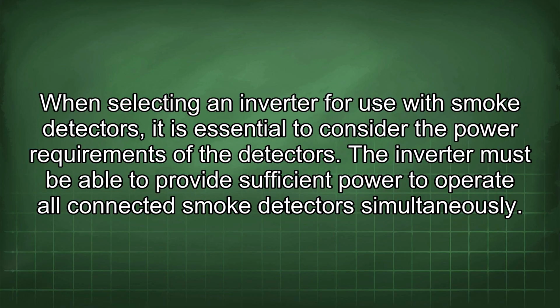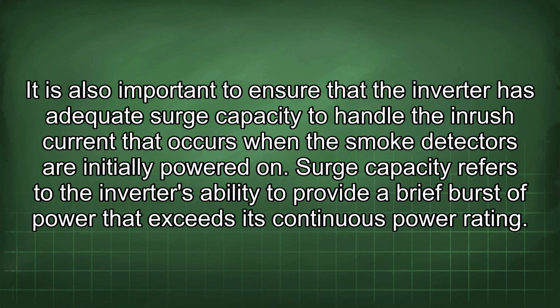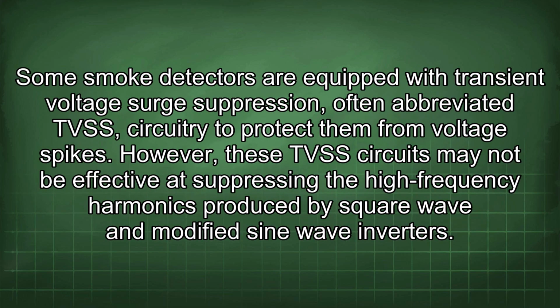When selecting an inverter for use with smoke detectors, it is essential to consider the power requirements of the detectors. The inverter must be able to provide sufficient power to operate all connected smoke detectors simultaneously. It is also important to ensure that the inverter has adequate surge capacity to handle the inrush current that occurs when the smoke detectors are initially powered on. Surge capacity refers to the inverter's ability to provide a brief burst of power that exceeds its continuous power rating. Some smoke detectors are equipped with transient voltage surge suppression, often abbreviated TVSS, circuitry to protect them from voltage spikes. However, these TVSS circuits may not be effective at suppressing the high-frequency harmonics produced by square wave and modified sine wave inverters.